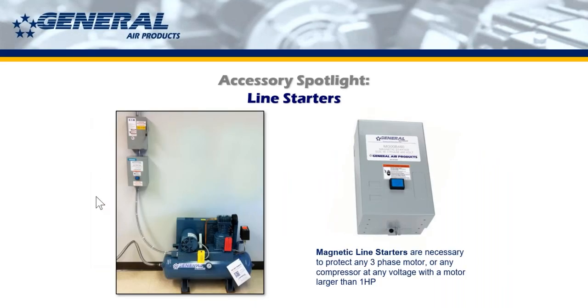Here's how one of the setups works. You can see that we have lines going. You have our industrial duty disconnect, which, just a quick sidebar, is a requirement in the standard now, as opposed to using a light switch, which is not allowed. Light switches are not allowed. You should really be using an industrial duty disconnect to hook up your air compressors. And right beneath that is where you see your line starter.